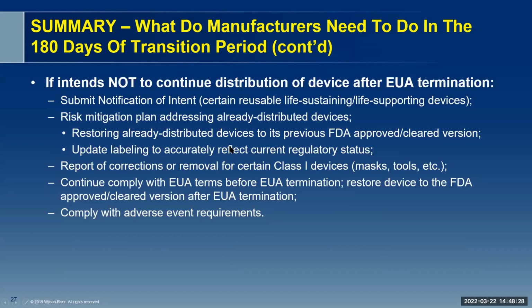What do you need to do if you do not intend to continue marketing your device after EUA termination? You need to submit your notification of intent if you have a reusable life-sustaining or life-supporting product. You need to have a risk mitigation plan to address your already marketed products. For certain products, you need to file a report of corrections or removal to the FDA. And you need to continue to comply with the EUA terms before the termination, and restore your devices and update your labeling after the EUA termination. You also need to comply with adverse event requirements for certain products.